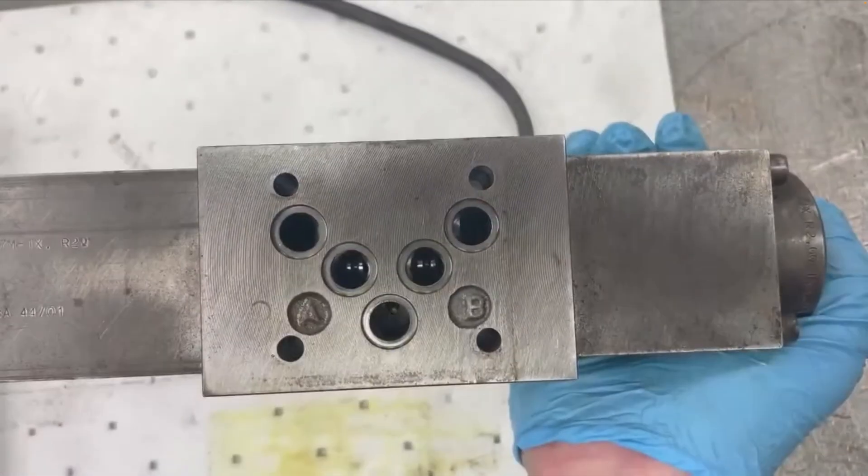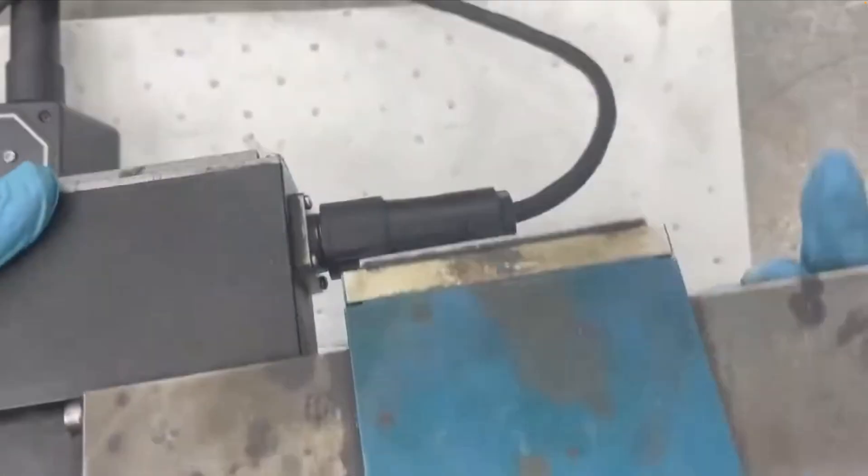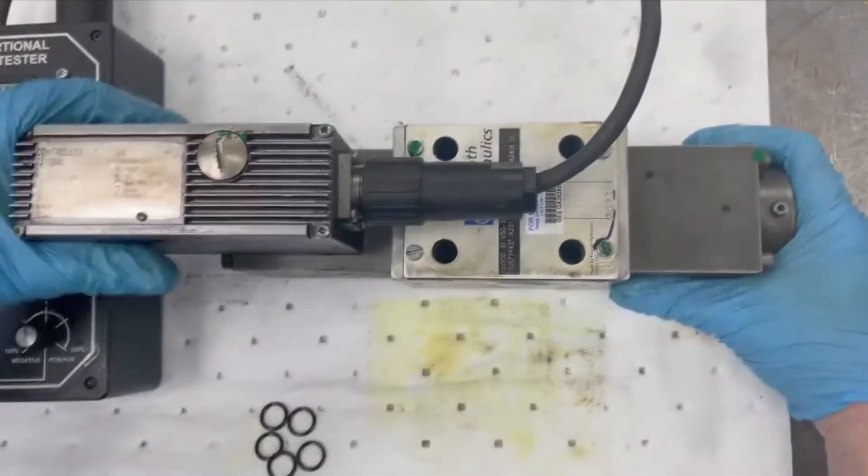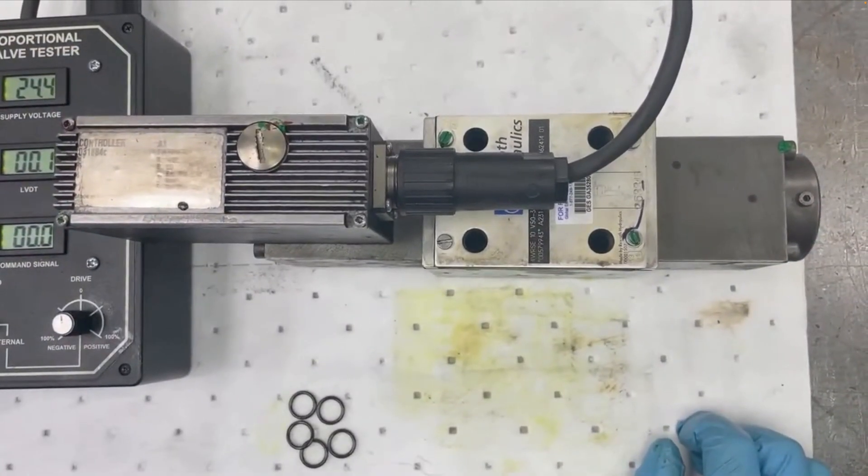So we're going to put this through a few more cycle tests. Then we'll disassemble the valve, service everything, change all the seals and components, service the onboard electronics for out of tolerance on aging electronics and parts, and then retest everything. And this valve will be fully repaired, tested, and ready for the customer.